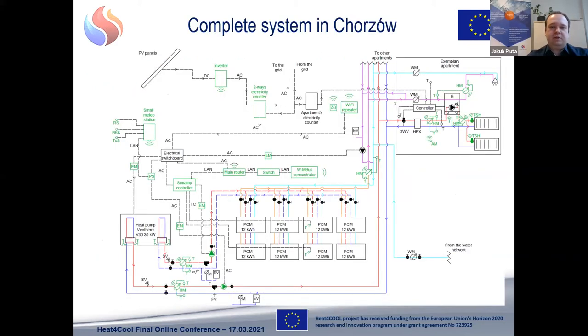On the scheme, you can see the complete system in our demo site. We have here the first part of the heating system between the heat pump and the apartments, the internal installation of the apartments, the heat batteries charging circuit, and the hot water distribution circuit to the apartment. In green, the monitoring devices are marked, like those to measure the efficiency of the system. We installed three heat meters in the basement and also three heat meters in the apartments, two for the space heating system and one for the domestic hot water system.